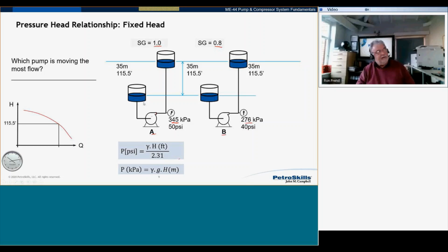Because they're pumping exactly the same amount of flow. Remember what we said? It's the amount of head that is the amount of energy. And if we look at the pump curve, we've got head against flow. By doing that, we've said that for that amount of head, in this case 35 meters or 115.5 feet, that will give us this much flow. So it's going to be the same. And that's quite important. Right, let's go down and just change the scenario a little bit.